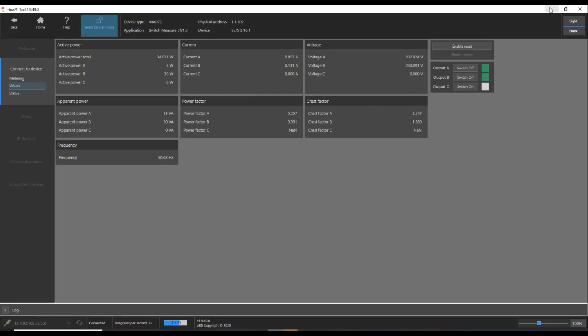I have a few alarms set up here - I can click here. I have an alarm set up because I've only a couple of amps here, just to show what happens. You can use this well: say you've switched on that channel, there should be power coming through - a normal lighting circuit might have 7 or 8 amps. If I switch it on and don't see that, I can trigger an alarm because something's not working. You saw how it triggered alarms up here every time I did something.